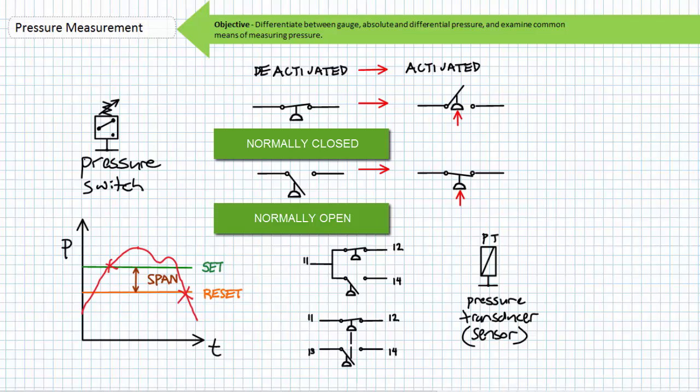The analog electrical signal of a pressure sensor can be used by a computer to make automated decisions about the process under control, necessitating no human intervention or monitoring. The schematic symbol for a pressure sensor is a box with a diagonal slash through it, sometimes with the letter PT for pressure transducer. You are aware of alternate schematic symbols pending manufacturer or country of origin. Note that pressure sensors are key to the operation of the previously mentioned digital pressure gauges. The internal circuitry in the digital pressure gauge converts the analog electrical signal generated by the pressure sensor to a number capable of being displayed on a readout or digitized and transmitted via a communication network.